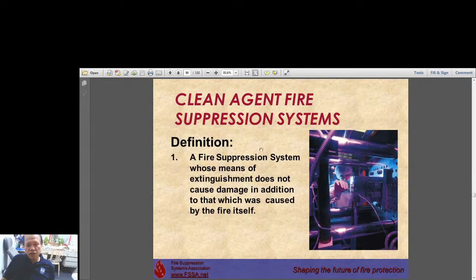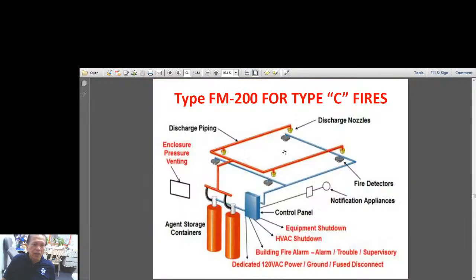Clean agent fire. So the definition is a fire suppression system whose means of extinguishment does not cause damage in addition to that which was caused by the fire itself. Okay, and here is the illustration for the application of the FM200. You know, when I was a young engineer, there was this halon, HALON. But it was found out that this substance halon is producing effects detrimental to the ozone layer. So eventually, it was banned because of this. And today, it is replaced by this FM200.